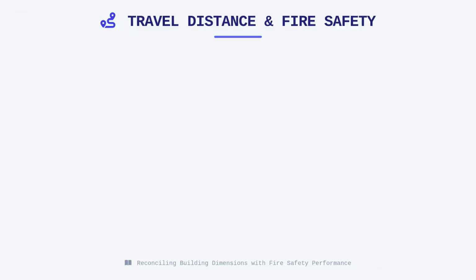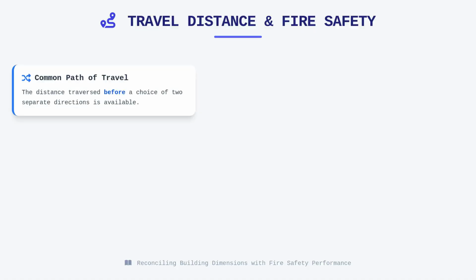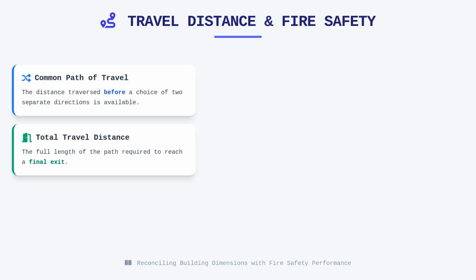Travel distance is another critical parameter that forces us to reconcile building dimensions with fire safety performance. Every occupant must have a path of travel that terminates at an exit, and the length of that path is constrained by specific variables in the code. We focus on the common path of travel, the distance an occupant must traverse before they are presented with a choice of two directions, and the total travel distance to reach an exit.